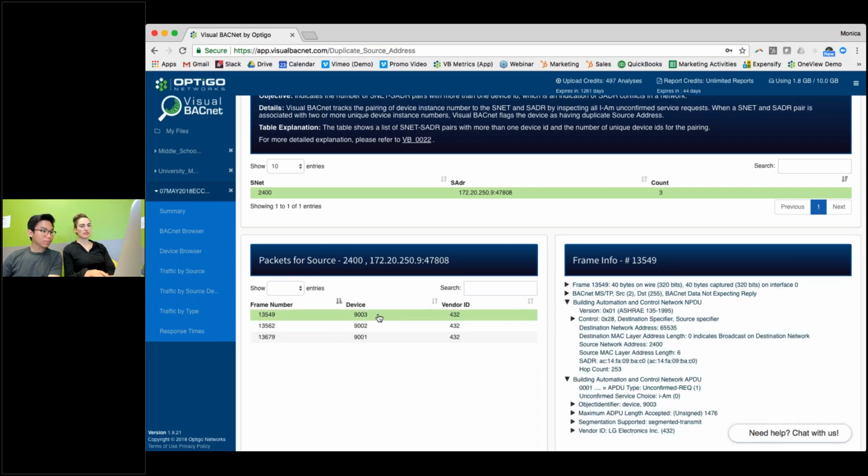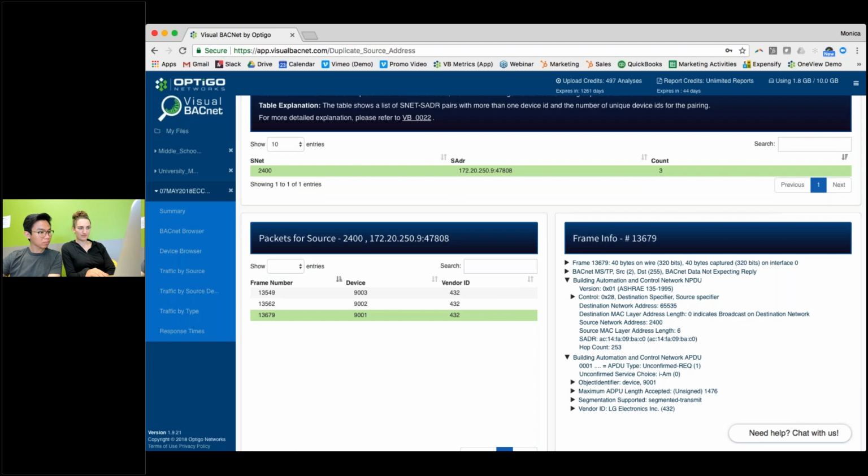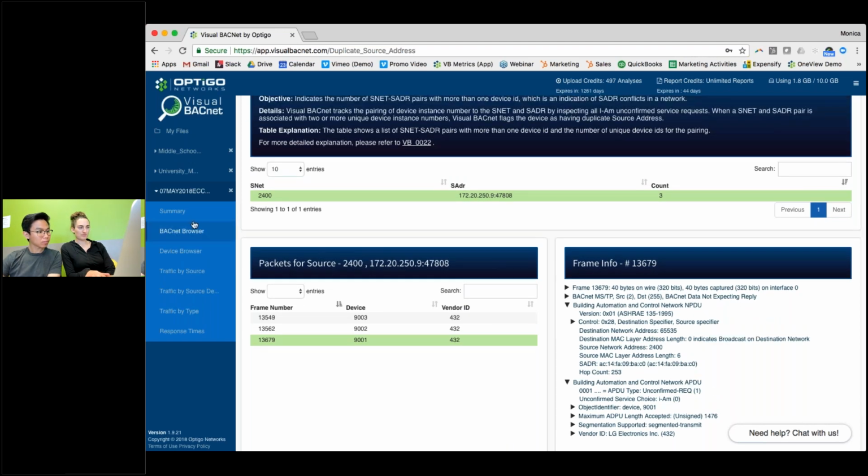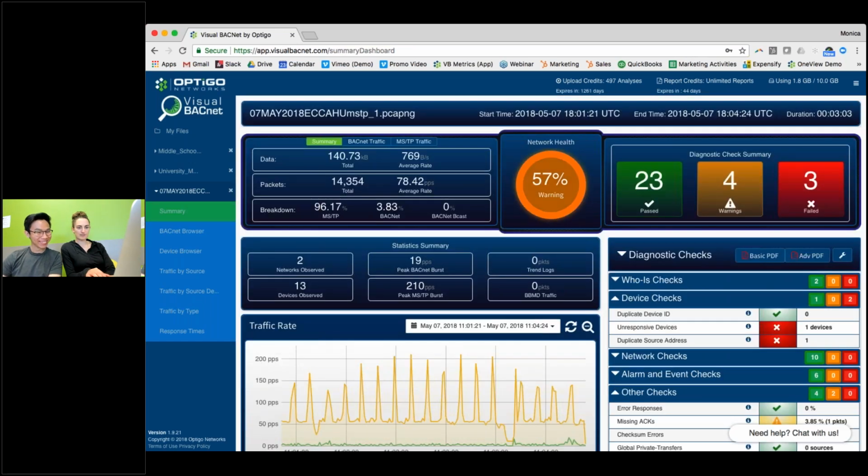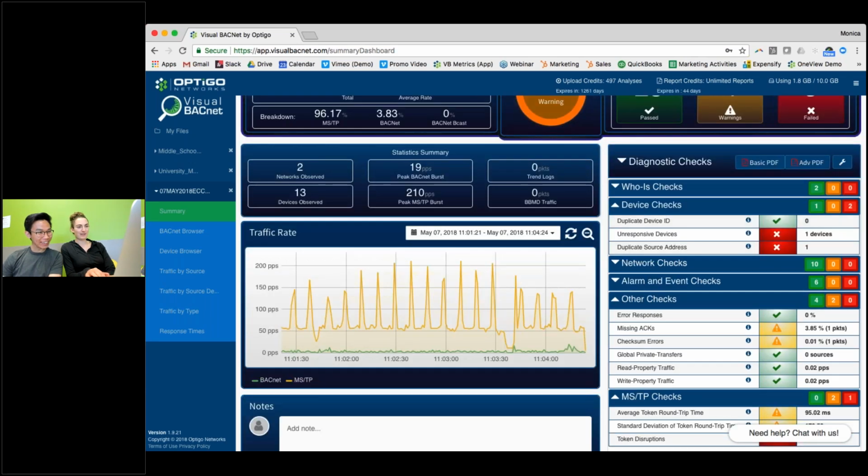Yeah. So basically go back to your device list. They should have prescribed different addresses and change them. Yeah, you should have 3 different ones. So the easiest way to fix this is to go to the one that's online, change its IP address, and then if you do a rescan of the network, a second one of these should show up, and you keep doing that. And then at that point, you'll have to figure out which ones actually belong to what IP address. But that would be the very first issue to go ahead and chase. You don't want your devices to be roommates, no shared addresses.